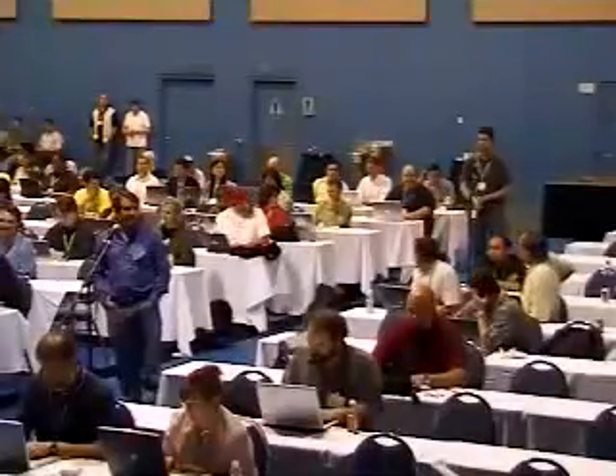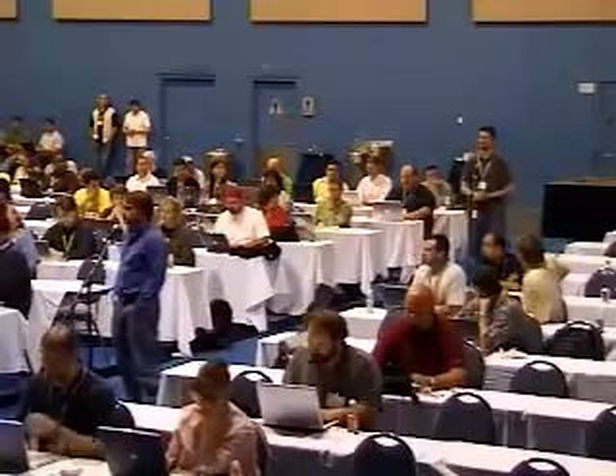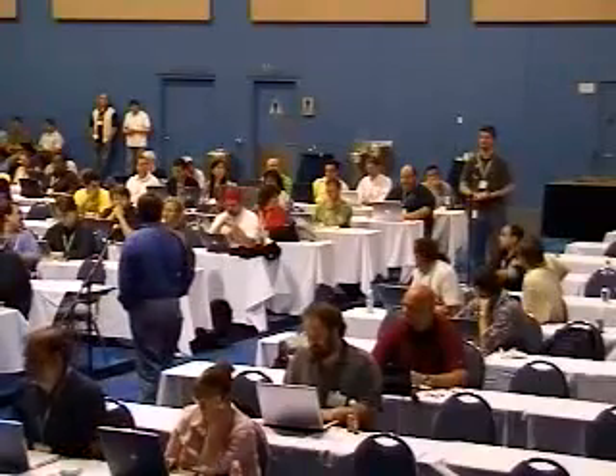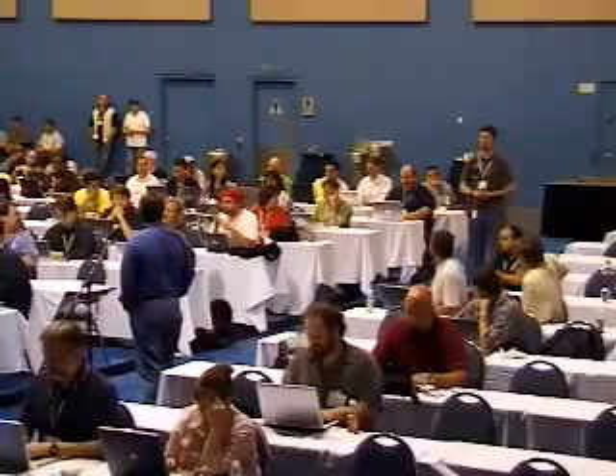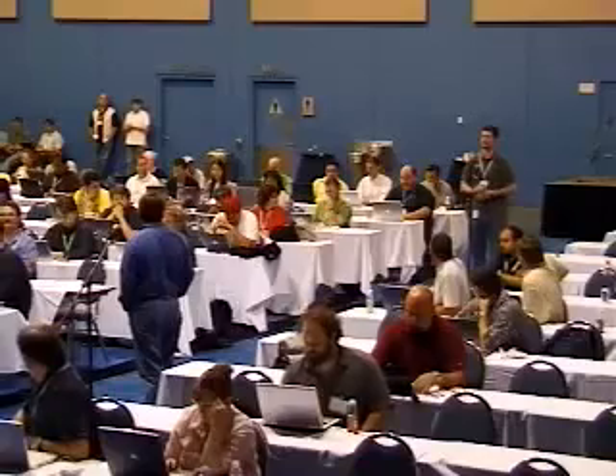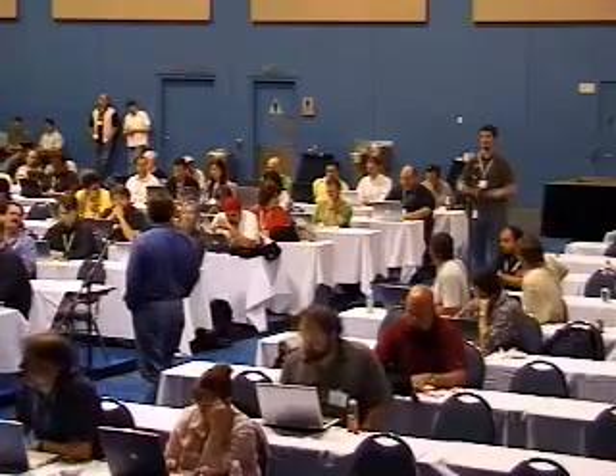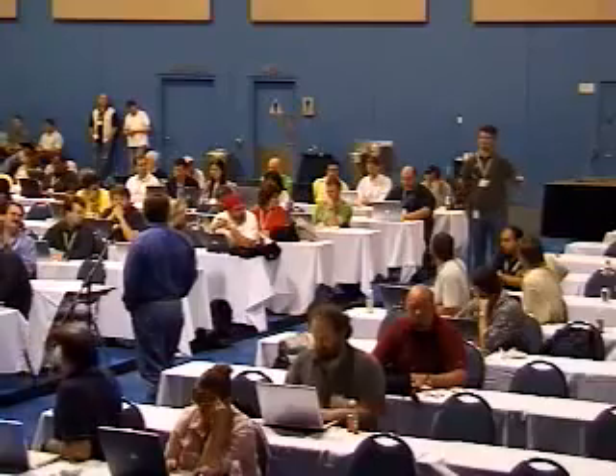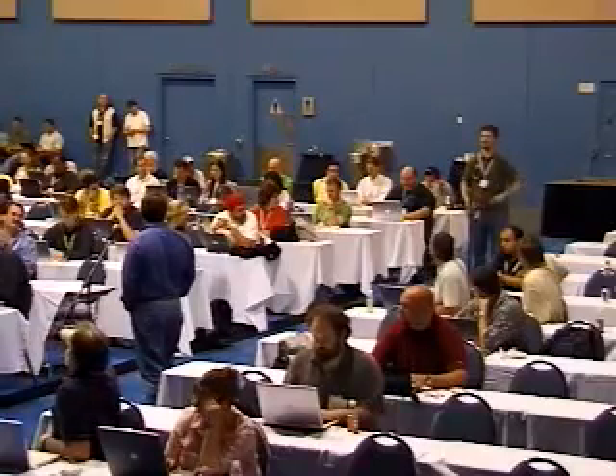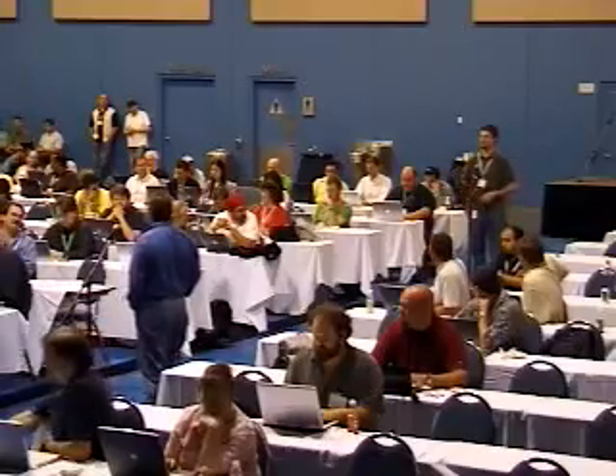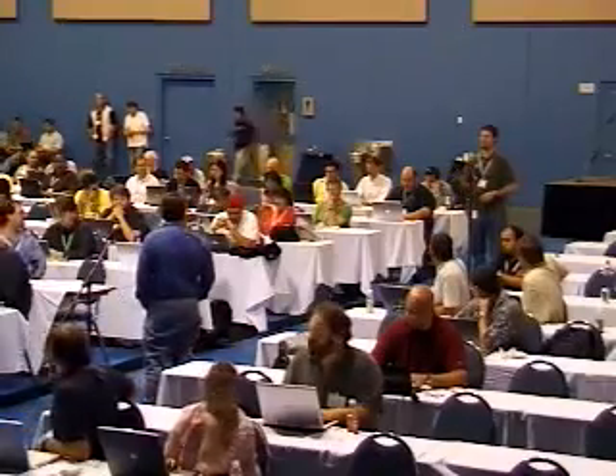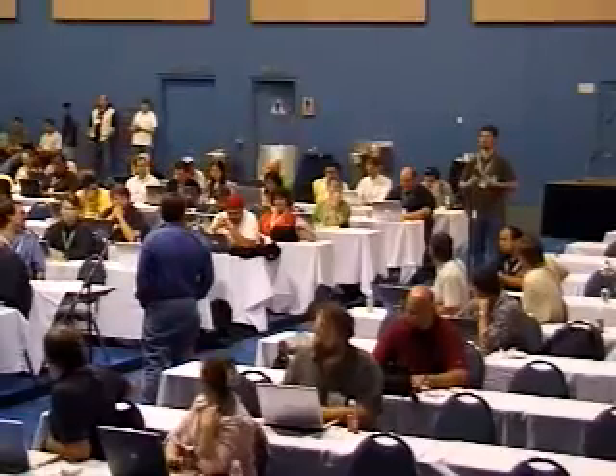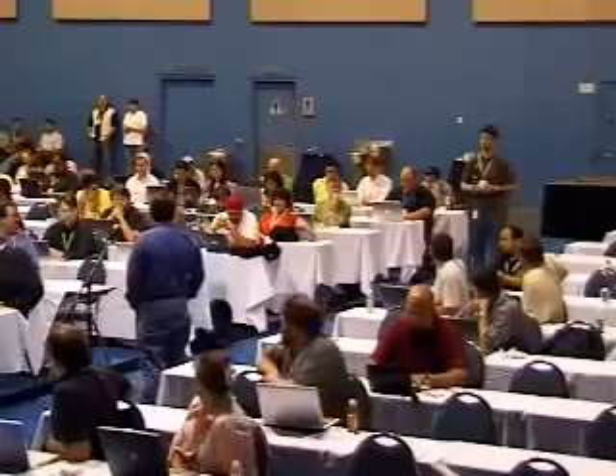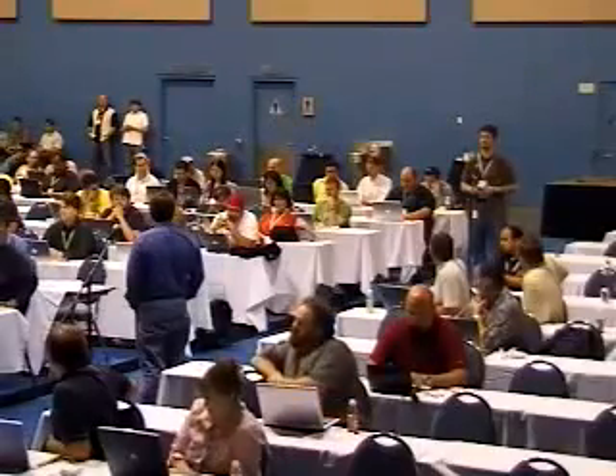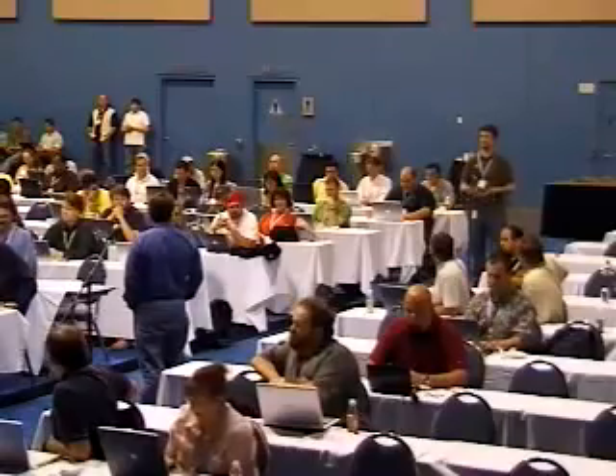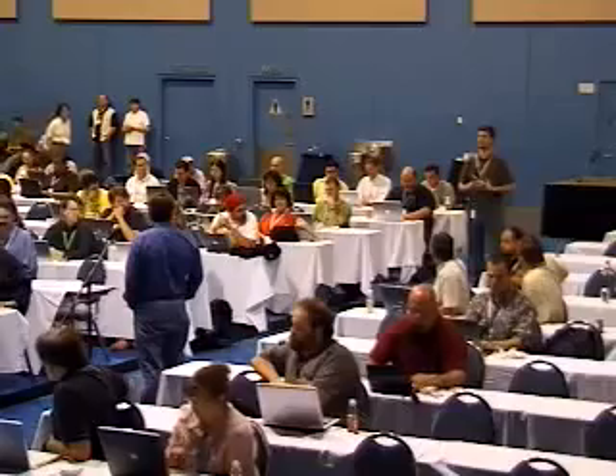Hello, my name's Derek Wise from GNI. We recently went through this with our data center in San Francisco. We deployed 1,008 IBM Blade centers in a 12 cabinet environment. We're currently taking up 2,500 square feet. We have a ping pong table and a soda machine and some other things in the adjacent cage that we left empty. I think 200 to 300 watts per square foot is insignificant. For us, we need somewhere between 2,000 and 2,500 watts per square foot delivered on the floor to get the space requirements down to the actual amount.